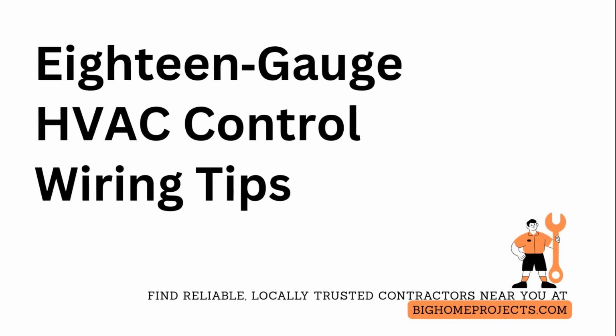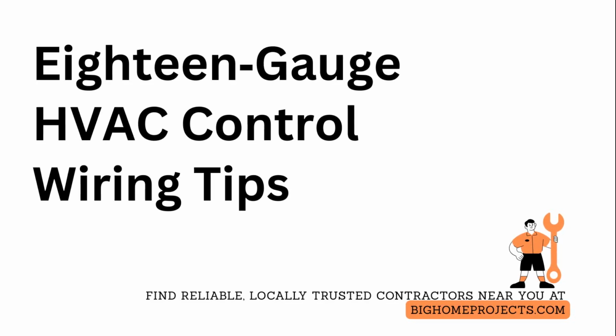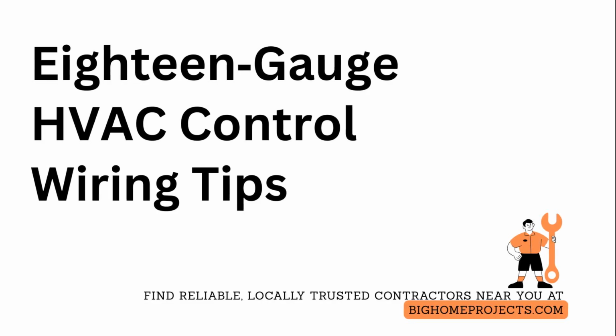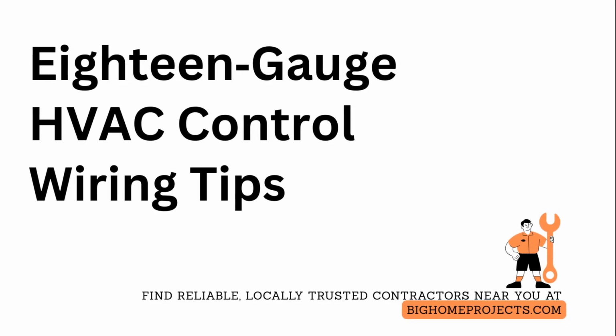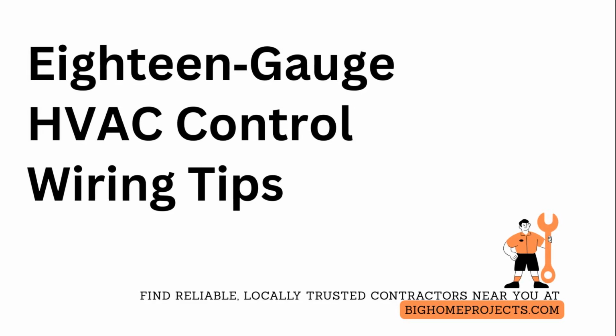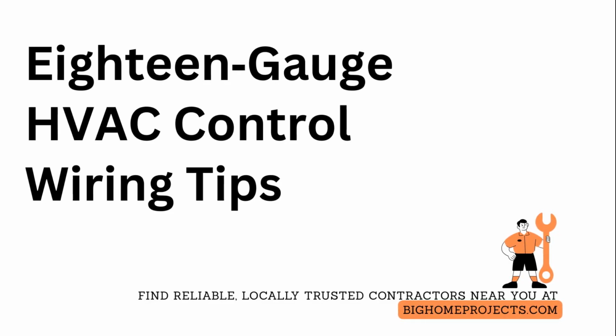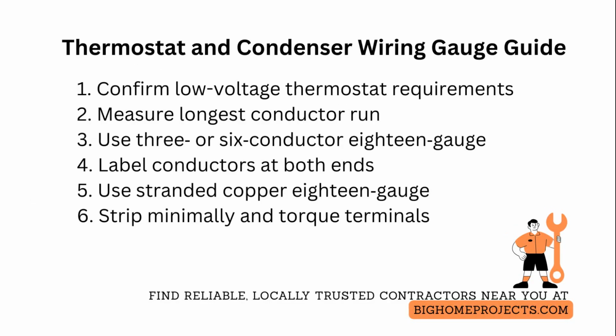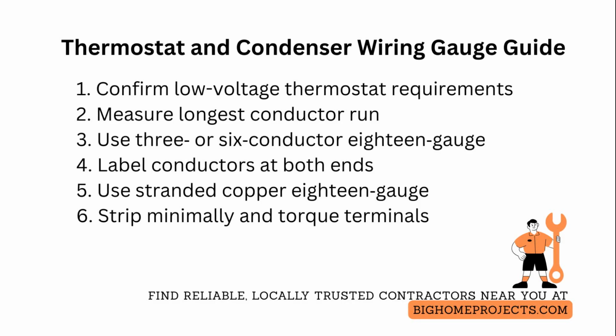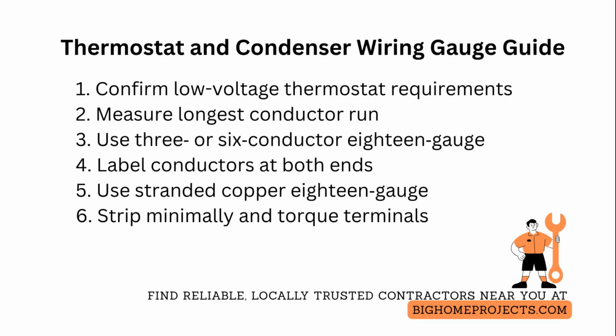Choosing the right thermostat and condenser wiring gauge matters more than most homeowners realize for safety, signal integrity, and code compliance. Here's why 18-gauge wire is the recommended standard for low-voltage HVAC controls. 18-gauge wire offers the perfect balance of current capacity and flexibility for thermostat and condenser control circuits. So start by confirming your thermostat requires low-voltage control and that the run length between the thermostat, air handler, and condenser is within code limits.